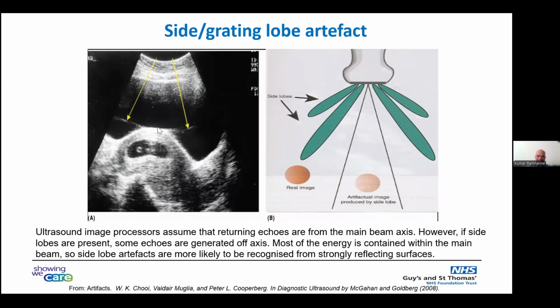And it's caused by the side lobe, which is coming out of the transducer, striking this bright interface, being returned to the transducer, and the scanner will think it's come from the main lobe, when actually it's come from the side lobe, and therefore will incorrectly position that signal as coming from the main lobe, the main beam, which is directed inside the bladder. So it's an incorrect representation of the interface in the bladder.